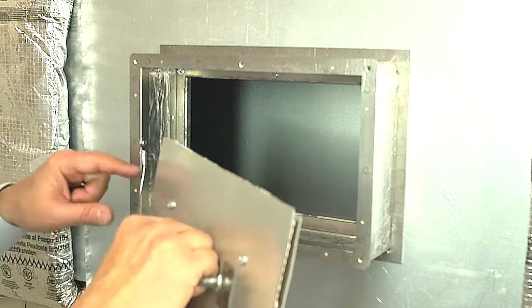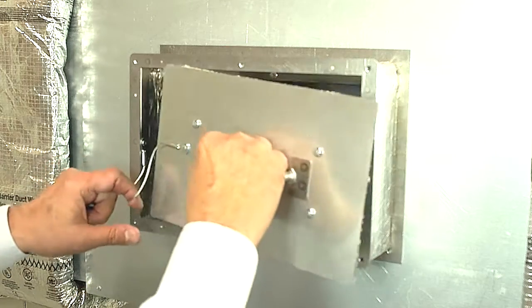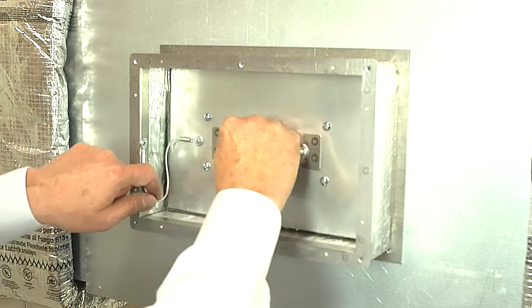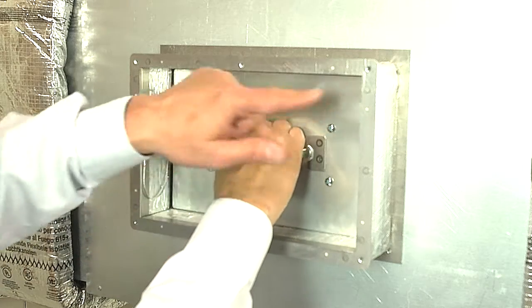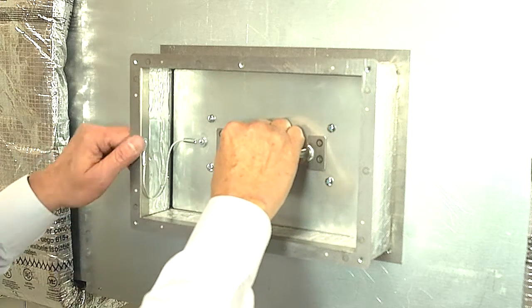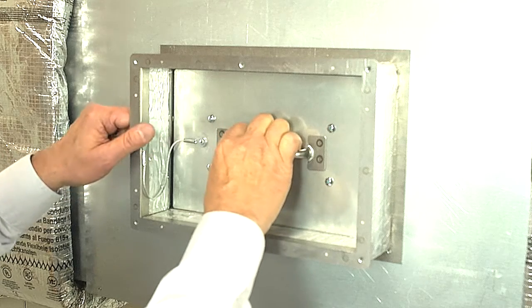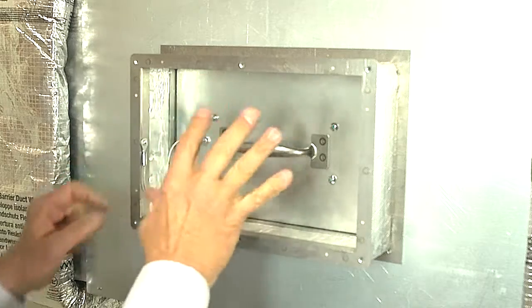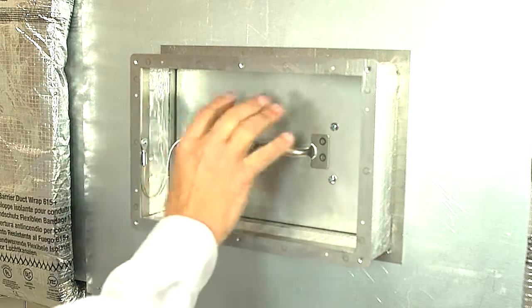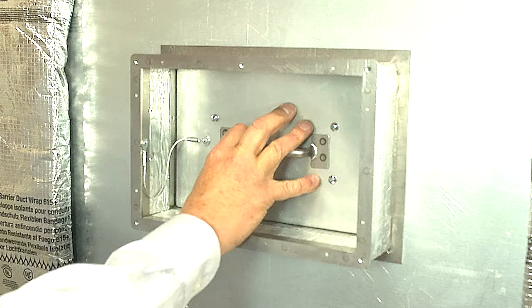Then we're going to take the grease plate and slide it in vertically into that steel channel that is part of the side frame. And then once we get to that point it's all the way in, we're going to give it a shove. And what that'll do is lock that silicone gasket. It'll fold back in and that is what makes it grease tight.